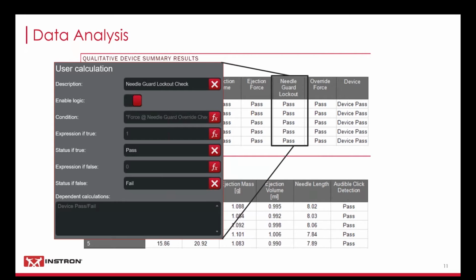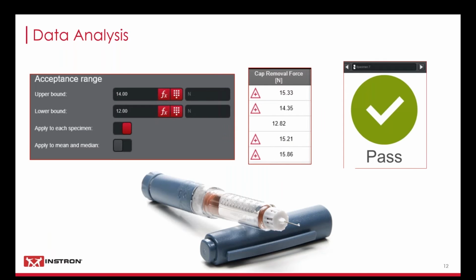This provides the operator powerful insight, quickly identifying failed specimens and the mode of failure. This information can help streamline failure analysis, directing the operator towards the most likely mechanical or functional issues. The software also gives clear visual indications whether a result is within a predetermined acceptance range, or whether the device passed or failed. The acceptance range is determined by the operator and can be conditionally set based on user specimen inputs.